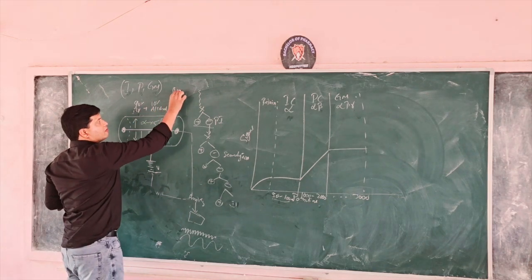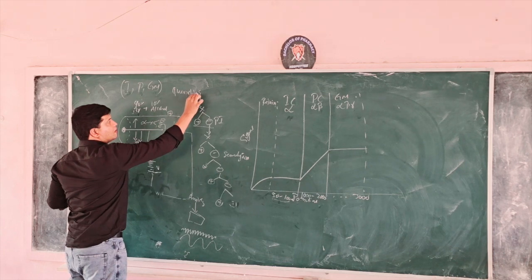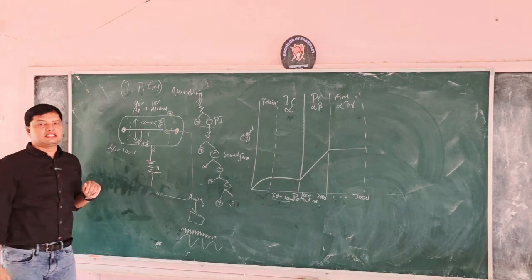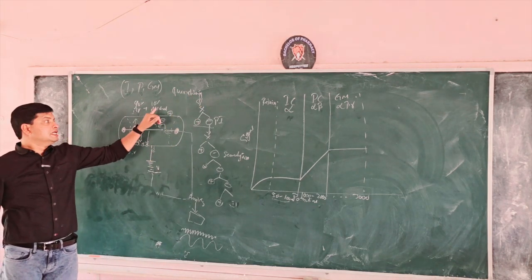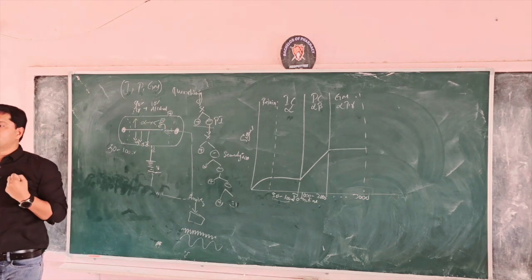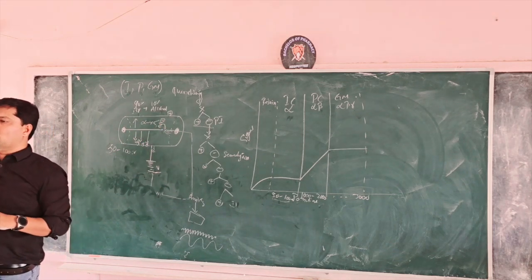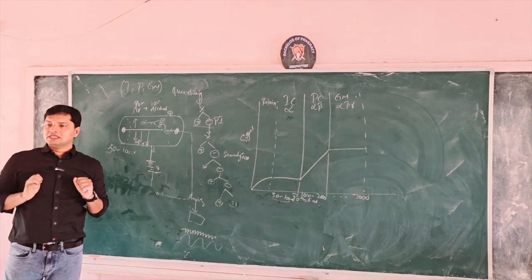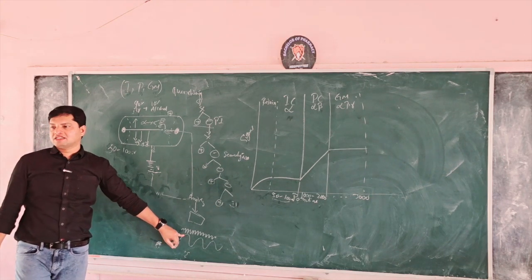Quenching. To avoid the false signal, we use quenching gas. This alcohol will absorb that signal. Ten percent alcohol will absorb the signal, and you won't get false signals.